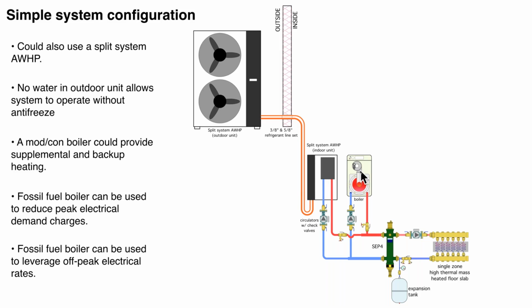And the boiler can be either an existing boiler or a new boiler. If it is a modulating condensing boiler, there's no need for mixing valves and no need for anti-condensation protection. You can see the boiler is simply piped up in parallel with the indoor portion of the air-to-water heat pump. Each has its own circulator with a check valve, each has a purging valve, and each just dumps into the hydraulic separator. And again, we can set up for constant circulation over on the right side.